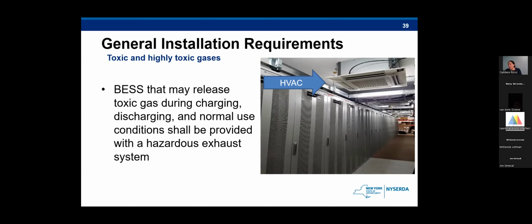Although, as we get to the later slides in the presentation regarding thermal runaway protections, you will see that many lithium ion batteries will install exhaust systems similar to this. It's just to meet other requirements in the code, not this one particularly. Lead acid batteries, on the other hand, can release toxic gas during operation, so they're always required to have ventilation.